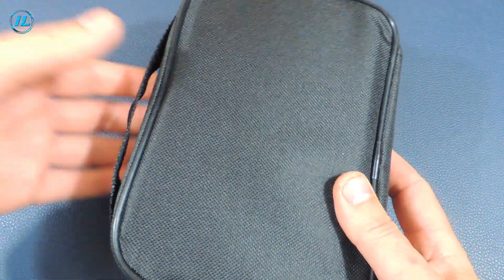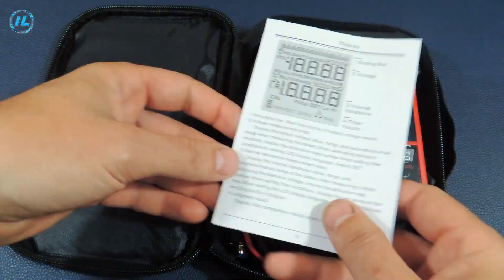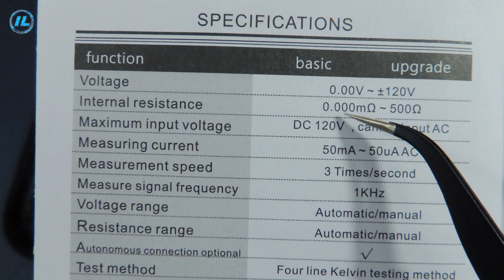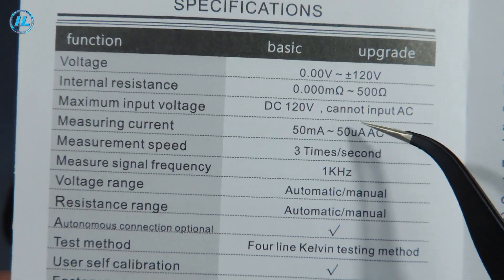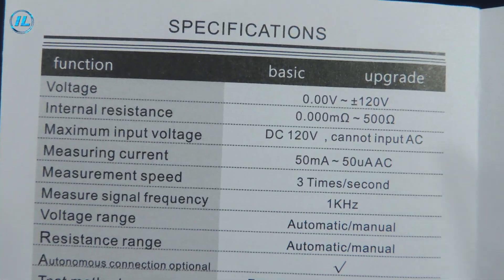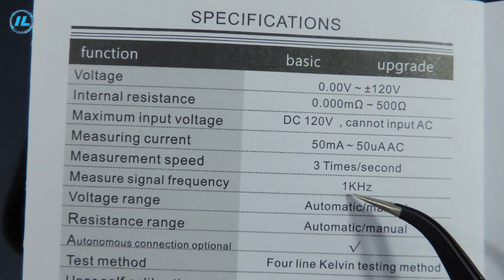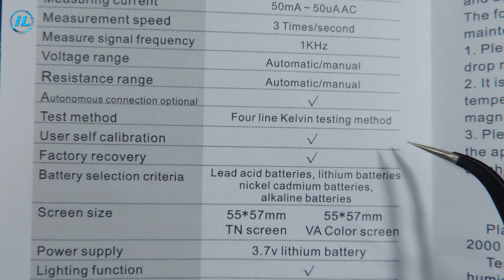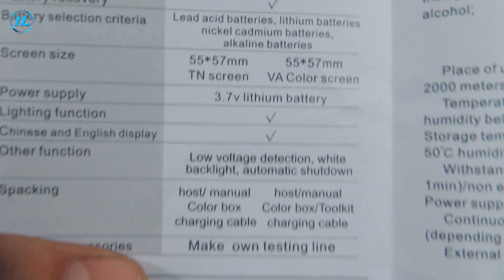Inside the box there is a cloth case in which it is very convenient to store the device and its accessories. Instructions are inside the case. The technical characteristics of this device are indicated here. The measured voltage is from 0 to 120 volts. The measured resistance is from 0 to 500 ohms. The maximum input voltage is 120 volts — it must be DC; alternating voltage cannot be applied. The current strength when measured is from 50 milliamps to 50 microamps. The measurement speed is 3 times per second. The frequency of the verification signal is 1 kilohertz. The measurement method is a 4-wire system. This device can measure the internal resistance of almost all types of batteries and accumulators: lead acid, lithium-ion, nickel-cadmium, and alkaline batteries.